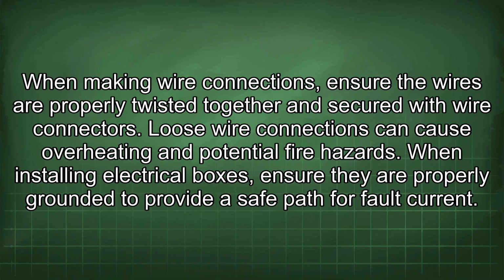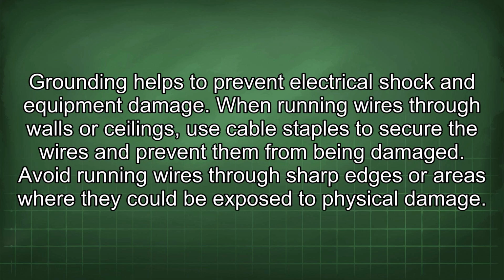When installing electrical boxes, ensure they are properly grounded to provide a safe path for fault current. Grounding helps to prevent electrical shock and equipment damage. When running wires through walls or ceilings, use cable staples to secure the wires and prevent them from being damaged. Avoid running wires through sharp edges or areas where they could be exposed to physical damage.